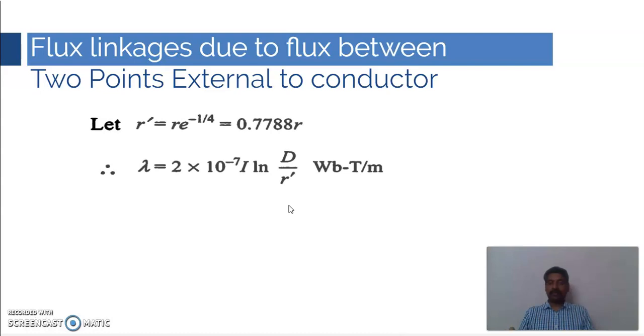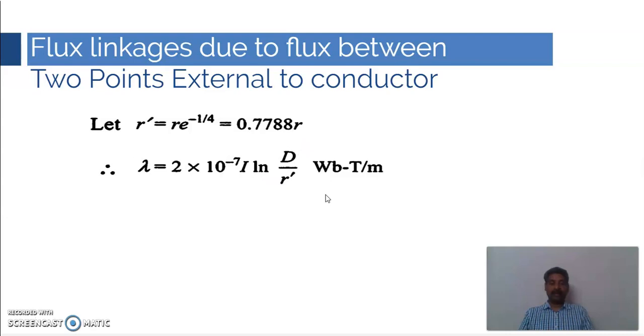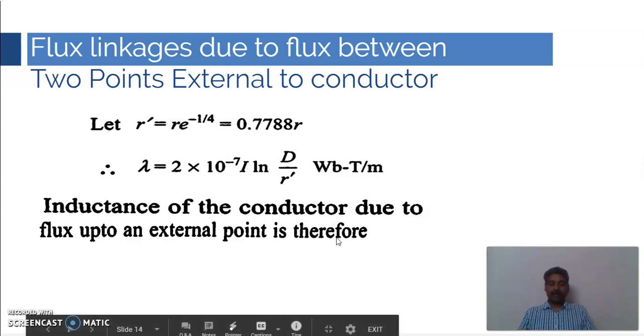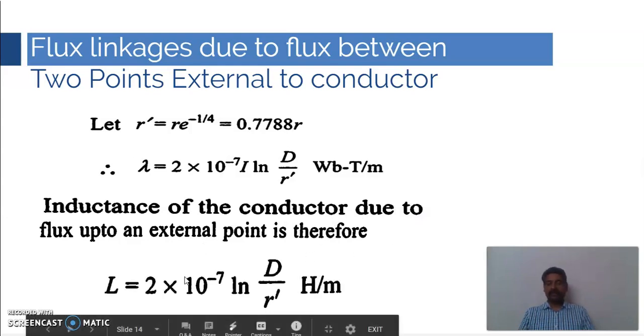We replace R × e^(−1/4) with a simple constant R'. Here R is the actual radius of the conductor, and R' is called the virtual radius, which is slightly less than the actual radius, given by R' = 0.7788 × R. Substituting R' gives the total flux linkage as λ = 2 × 10⁻⁷ × I × ln(D/R') Weber-turns per meter. The total inductance is L = 2 × 10⁻⁷ × ln(D/R') Henry per meter, accounting for both internal and external flux.